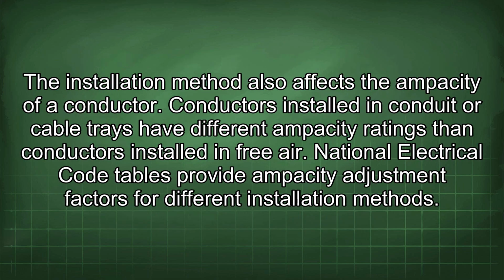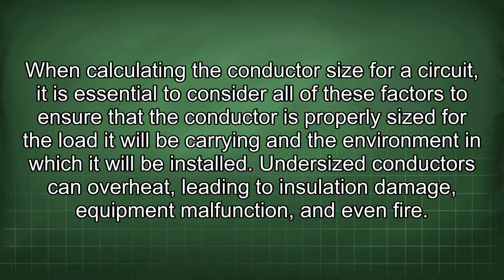The installation method also affects the ampacity of a conductor. Conductors installed in conduit or cable trays have different ampacity ratings than conductors installed in free air. National Electrical Code tables provide ampacity adjustment factors for different installation methods. When calculating the conductor size for a circuit, it is essential to consider all of these factors to ensure that the conductor is properly sized for the load it will be carrying and the environment in which it will be installed. Undersized conductors can overheat, leading to insulation damage, equipment malfunction, and even fire.